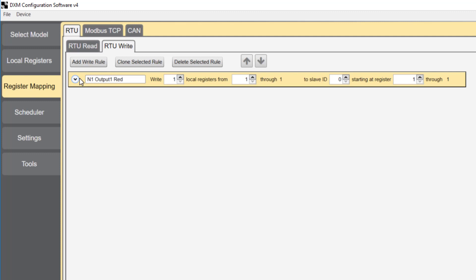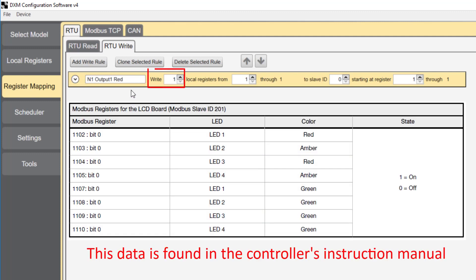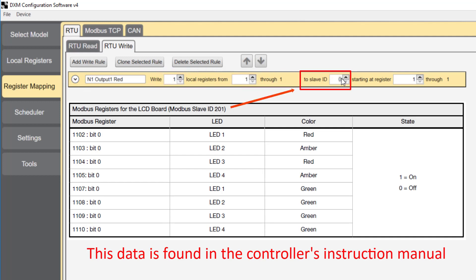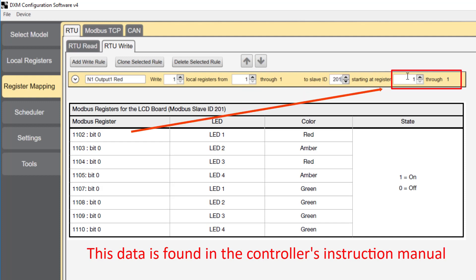Let's set this up. We're going to write one register from local register 1. We're writing that data to slave ID 201, which is the LCD board, and we're writing that data to register 1102, which is the number 1 red LED.